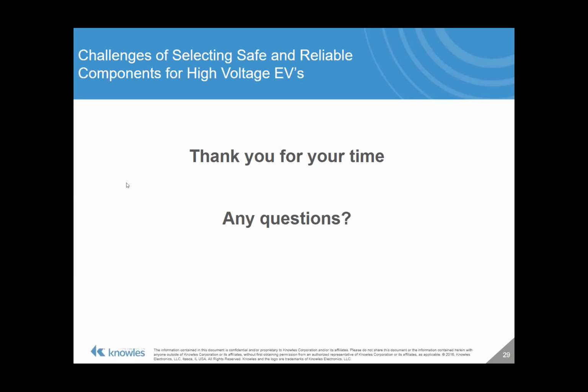Someone said, when we say test voltage, are we referring to any end-of-line testing or general validation testing? Depends on the voltage we're talking about. A certain amount of the dielectric withstand voltage is end-of-line testing, but we also will have general validation testing as well. It's not practical, for instance, to test 100% at 60 seconds, so that would be a validation test done on a batch basis. Depends on the test, depends on the product. Generally, I was referring to end-of-line testing, but not in every case. If you want it a bit clearer, feel free to contact me and we can pick up on your specific requirements.